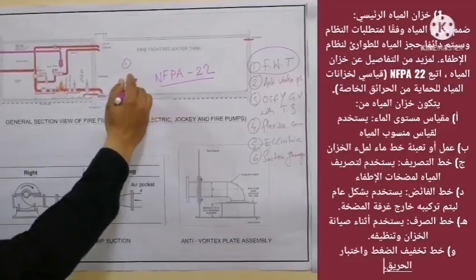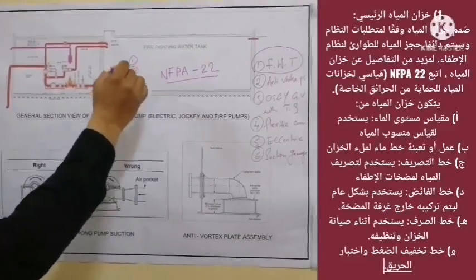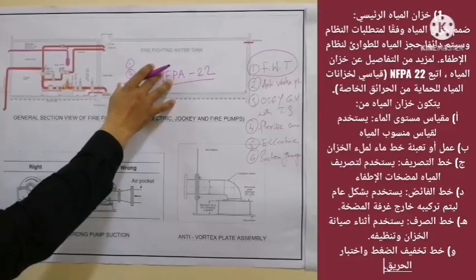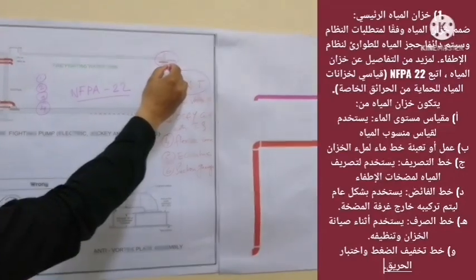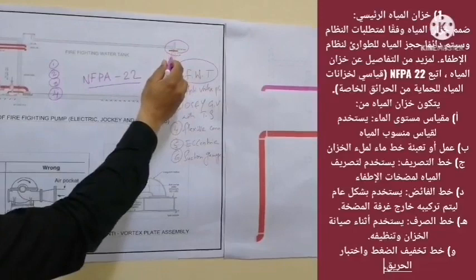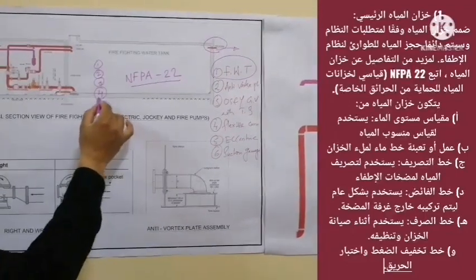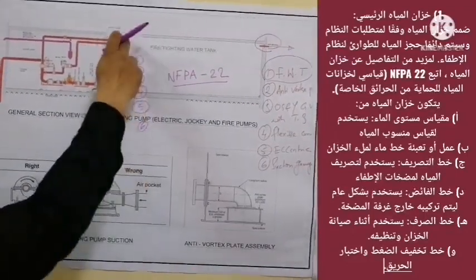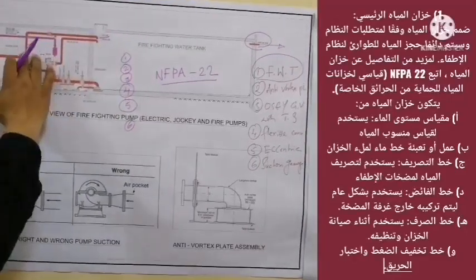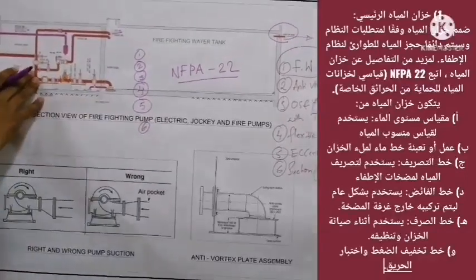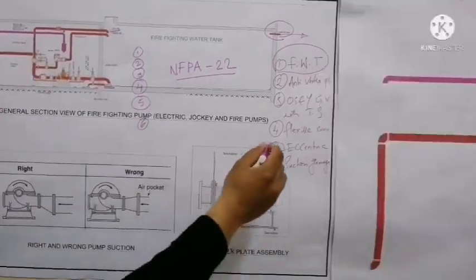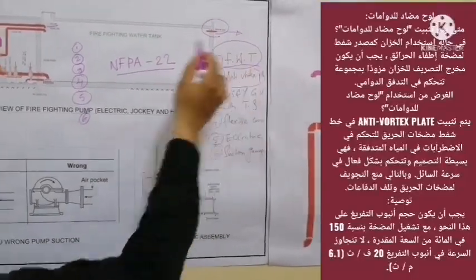Number two, we have a makeup water or filling water line to fill the tank. Number three, we have a discharge line used to discharge water to the fire pump. Number four, we have an overflow drain — this is used in case of overflow and is to be installed outside of the pump room. Number five, we have a test and relief line — this detail we will discuss when we start the discussion for the discharge line.